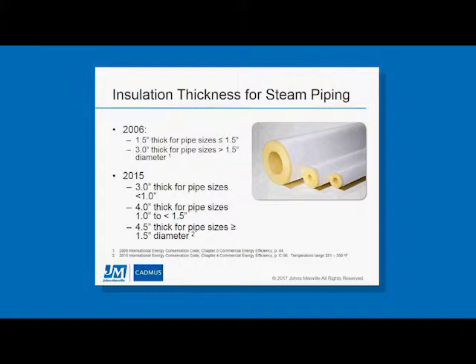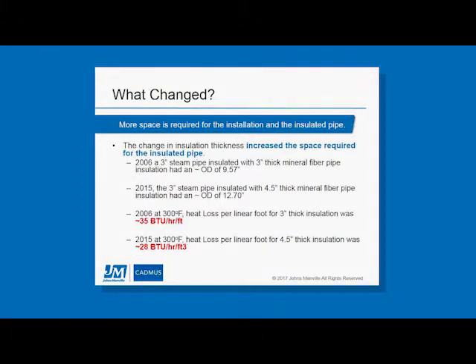Now it was double the insulation thicknesses for pipe size less than 1 inch. It now needed to be 3-inch thick insulation, 4-inch thick insulation for pipe sizes 1 inch to less than 1.5 inches, and 4.5-inch thick insulation for steam piping greater than or equal to 1.5 inches in diameter. The implication here is that you needed much more space for your insulated pipe.